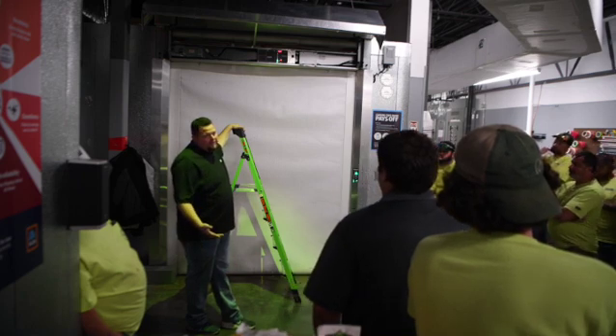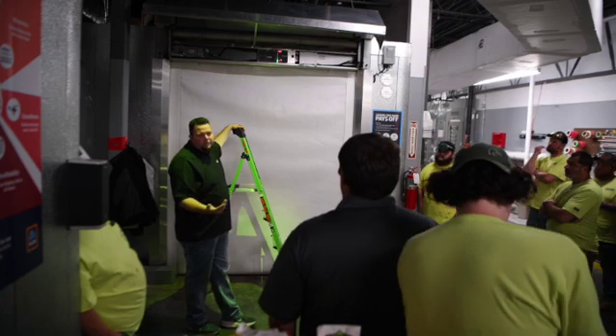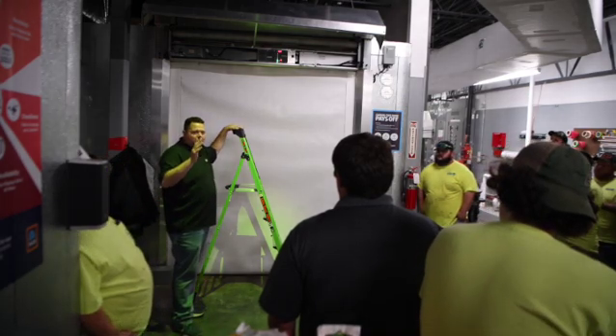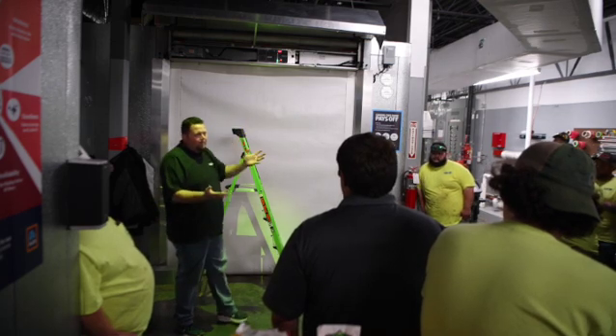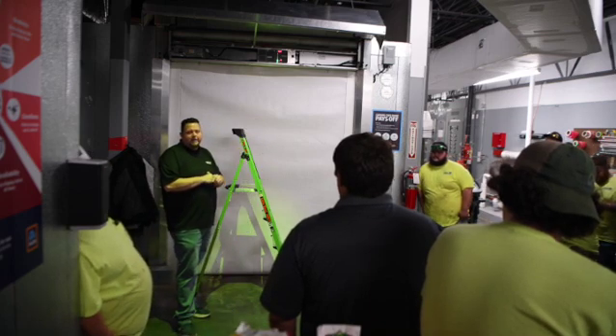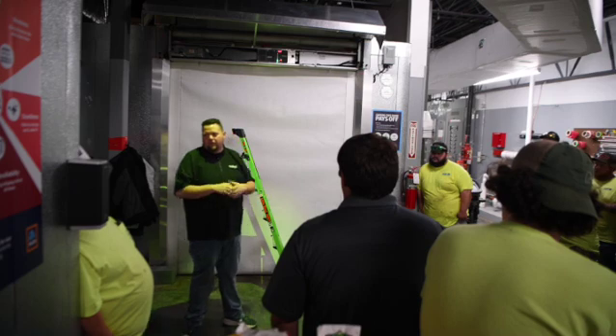The reason for that is because 99% of the time it's not. We sell, especially these older type doors, we'll see where a tech somewhere, Walmart's bad about it, their tech won't call and they say the motor's bad. Well, what is that motor? The motor's probably one of the most expensive parts on the door. They're ordering that when it's a little brake relay on that circuit board. So they get a new motor, put it on, and it still doesn't do anything. It's a big difference in price, but call us before you ever go to a motor.